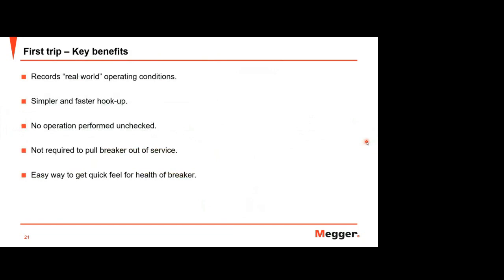Okay, and this is the key benefit of the first trip. Some of them were already explained, but yes, you can record real-world operating conditions, with a simple and faster hookup, no operation performed unchecked, and it does not require the breaker to be fully out of service because it is just a short time. You can just do a reclose, very short, and it is an easy way to get a quick feel for the health of the breaker. So this is a very good way to analyze your breaker condition with very short testing time.